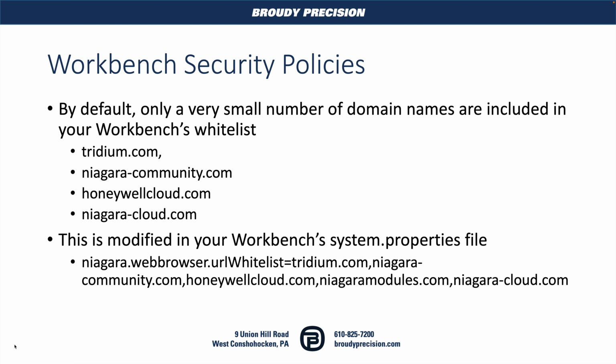But we have the ability to modify this list through the system.properties file of our Workbench. An important thing to note here is that this only applies to the Workbench that you make this change on. It's not a change that we're making on our station. It's just in the Workbench that we're connecting with. So if you needed to make this change, you very likely would need to make it multiple places. So just keep that in mind.